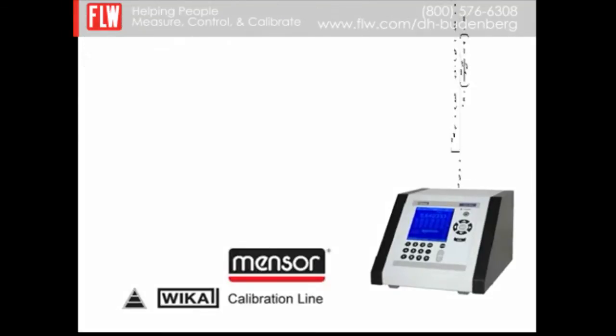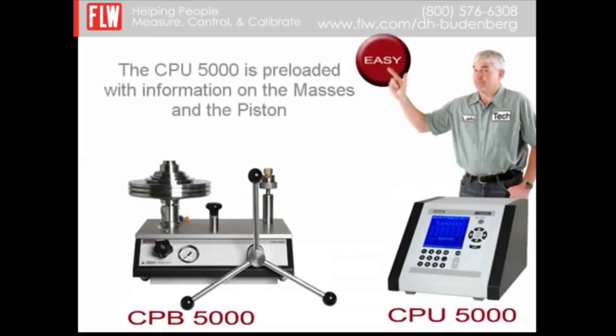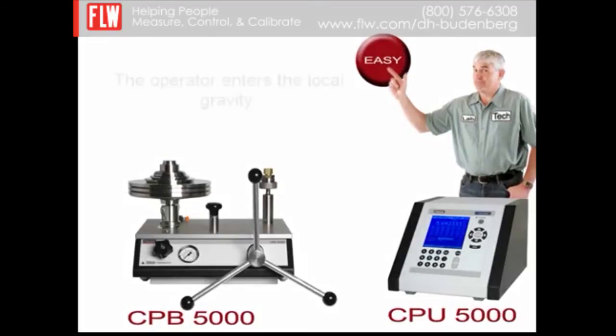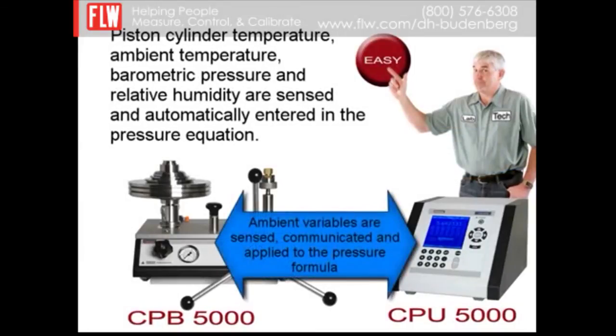the CPB5000 dead weight tester, the masses, the piston, and even your local gravity can be programmed into the CPU5000. The operator has the ability to enter in any local gravity based on his specific location. Piston cylinder temperature, ambient temperature, barometric pressure, and relative humidity are sensed and automatically entered in the pressure equation.